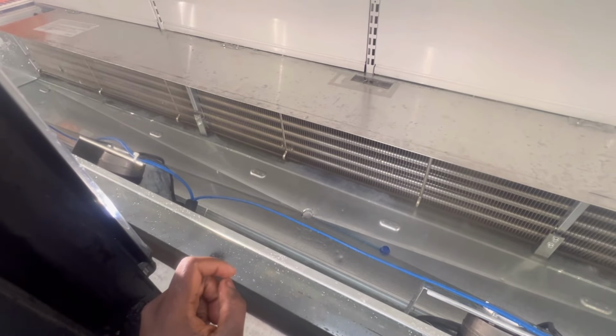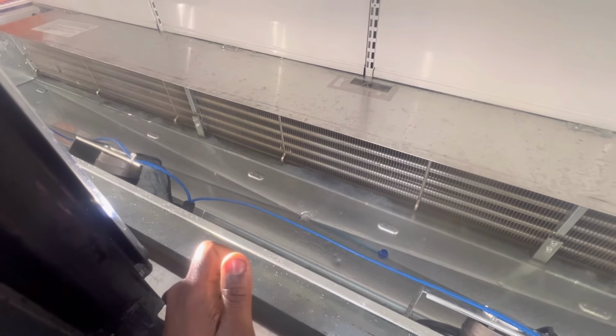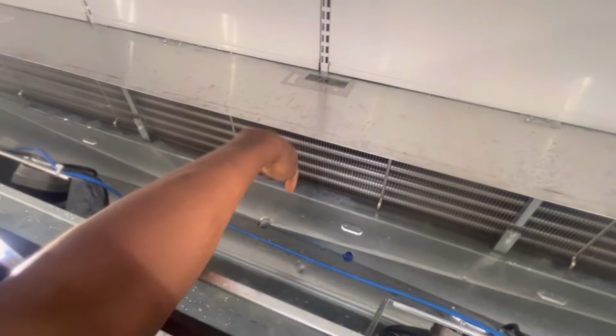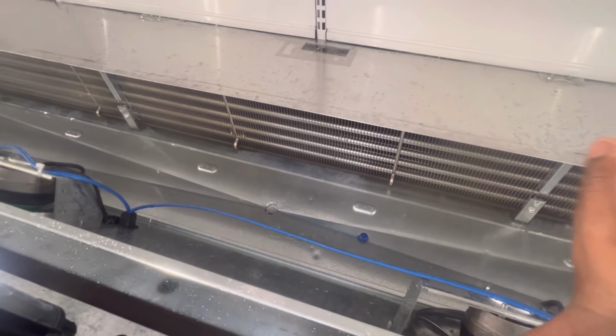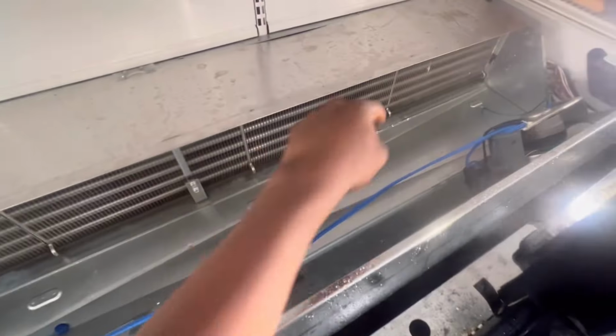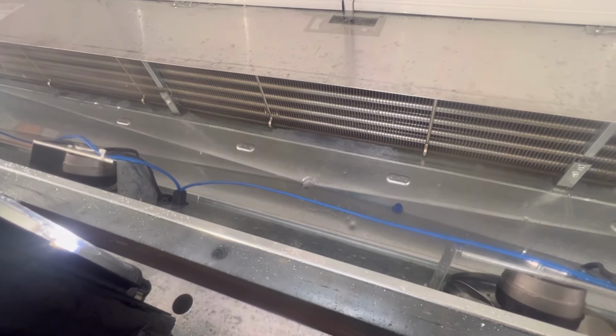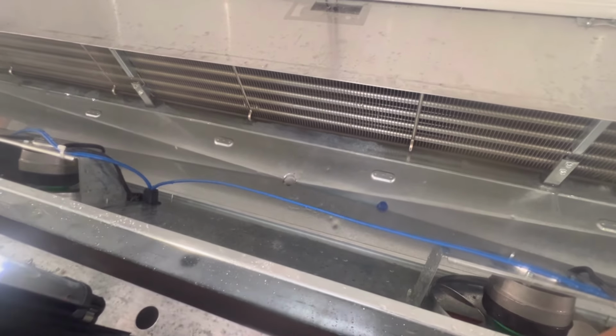I might need to start keeping some type of drain heater, because I could have hooked it up possibly somewhere right here, spliced it in, and had a drain heater down at the pipe to prevent freeze ups and all that. Typically that's normally used, or they usually have a strip that runs across the case, but if it happened again, I'd have to go that route just to prevent it.